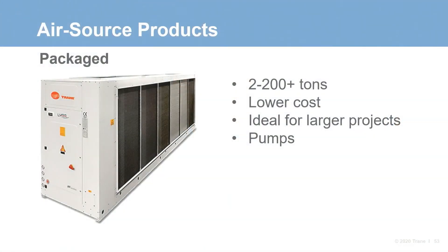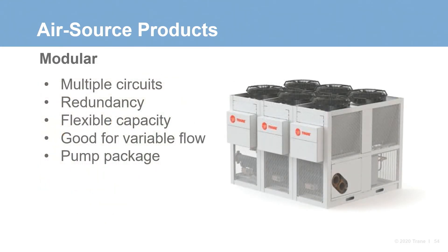Packaged heat pumps come in a wide range of nominal sizes and configurations, mostly utilizing scroll compressors. Smaller units are typically a single circuit, while larger units feature dual refrigerant circuiting. Packaged units can be advantageous for larger projects as they can be lower cost at larger tonnages, and can offer options like low sound fans and pump packages to accommodate site requirements. Modular heat pumps offer flexible sizing and footprint configurations, typically in nominal tonnages from 10 to 80 tons per module. When redundancy is required, modular units accommodate this with multiple independent circuits or additional modules. Because they use multiple units linked together, they can be a good solution for variable flow systems, and options like pump packages and glycol systems can easily be incorporated.